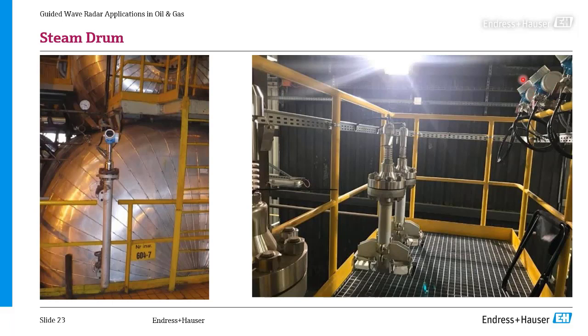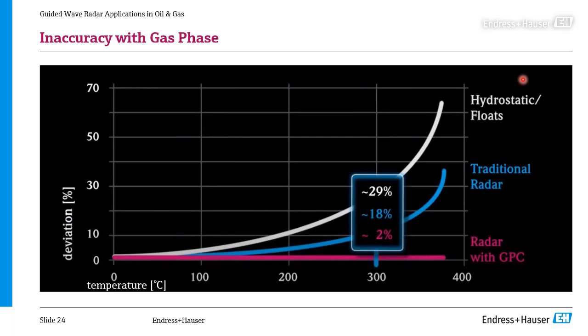What's the issue with boilers? You can have huge inaccuracies in your measurement in the gas phase. Here's an example: at 300 degrees Celsius, a traditional radar shows a deviation of 18%, and it can go even higher. Hydrostatic floats show even higher deviations. Now if you look at a radar with GPC, you end up with just 2%.